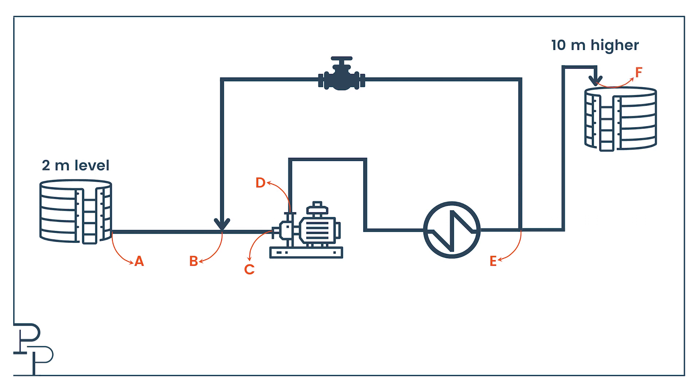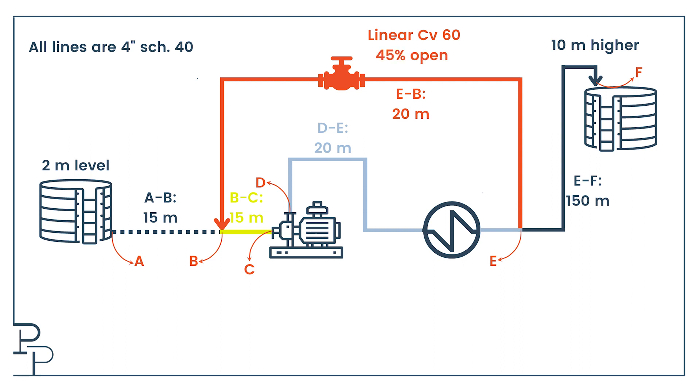If we are to build system curves, we need more details and the full geometry of our system. Let's say all our lines are four inch schedule 40, giving us the inner diameter. Portions AB and BC are both 15 meters long. Portion DE excluding the heat exchanger and portion EB will both be 20 meters long. Portion EF will be 150 meters long. The valve has a linear characteristic with a fully open CV of 60, and we're going to leave it at a constant 45% opening.